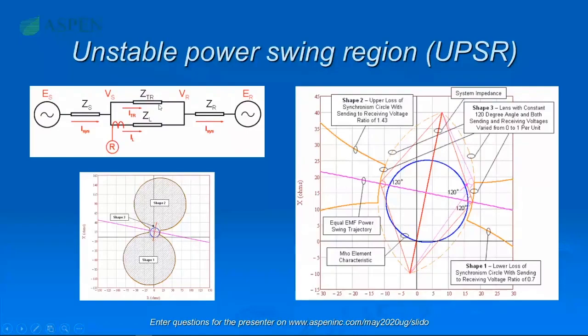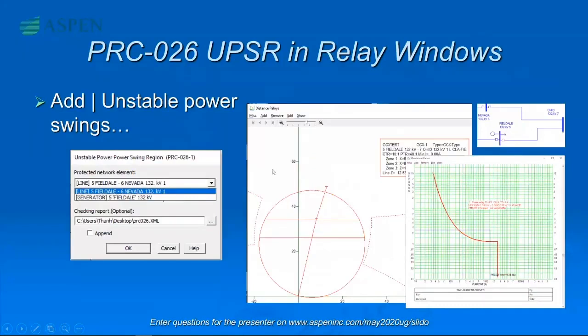What you get is a report on the right-hand side with graphics and source impedances. The highlighted section indicates whether it 'trips during stable swing' — yes or no. The program used a simulation-based approach to come up with a yes/no answer. It reduces the whole system to two buses and plays out that swing, deriving the dumbbell shape. For each point on that scenario, the program applies the relay simulation to the voltage and current observed at that point and reports whether the relay tripped at any of those points.